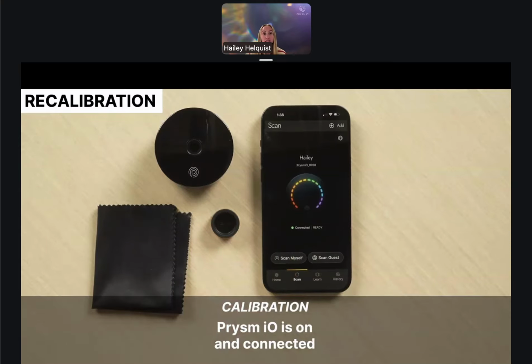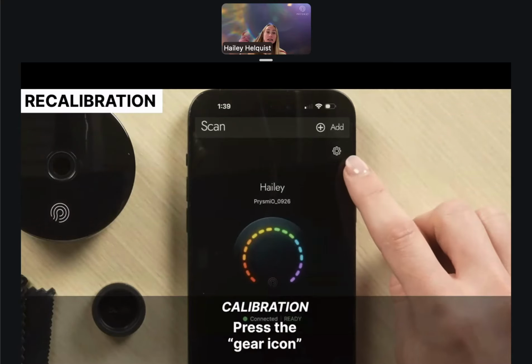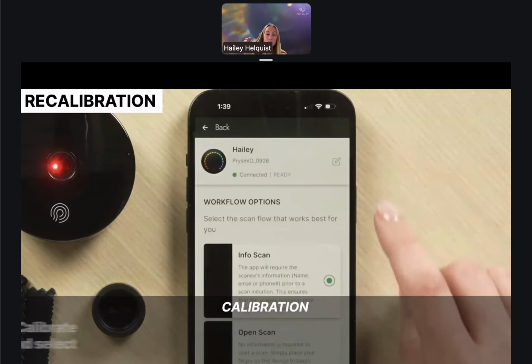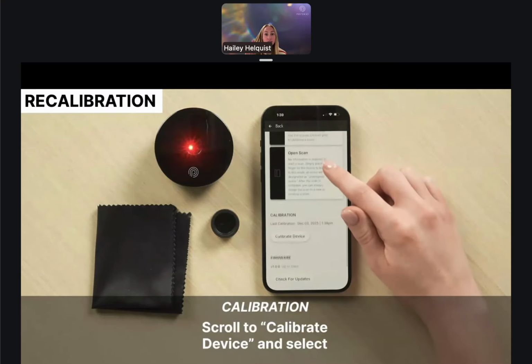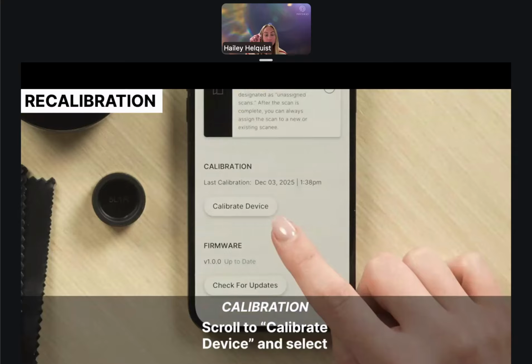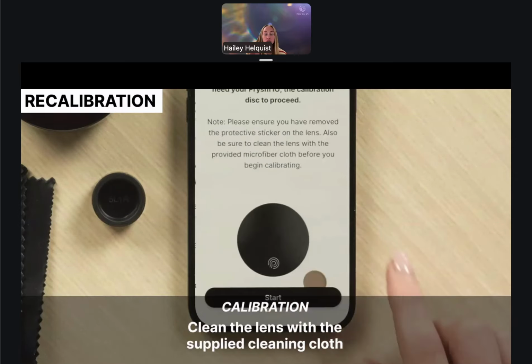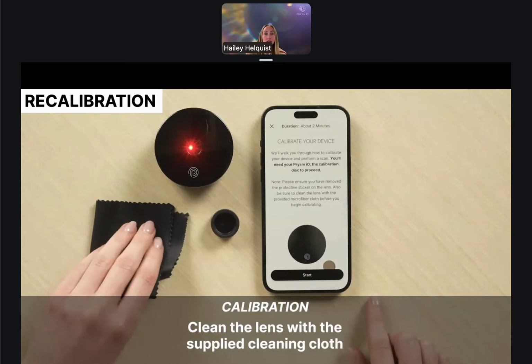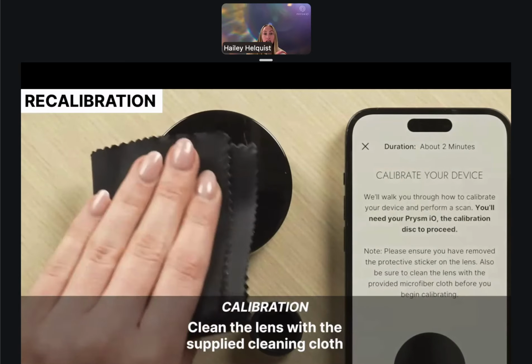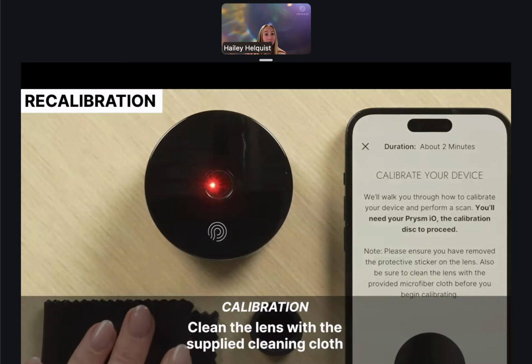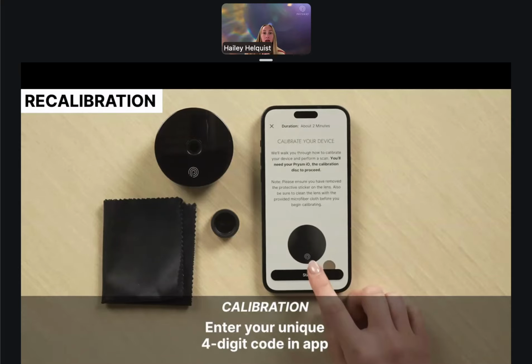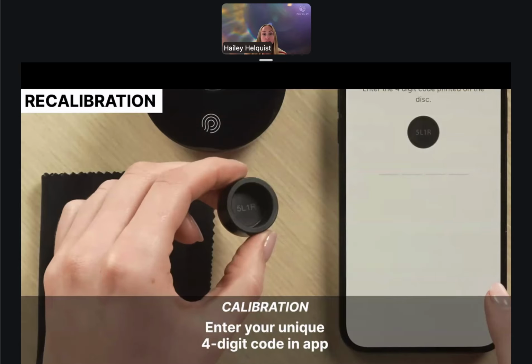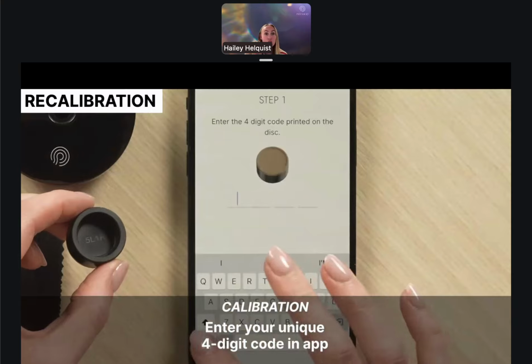You need to make sure your device is connected, and then you'll press that gear icon in the top right-hand corner. And then when you scroll down, there should be this calibrate device button right there. That's how you can recalibrate your device. We will have some easier ways to check calibration and to recalibrate as part of our next app update that Jessie will highlight. But from here, the calibration process is the same as it was before, so no difference.